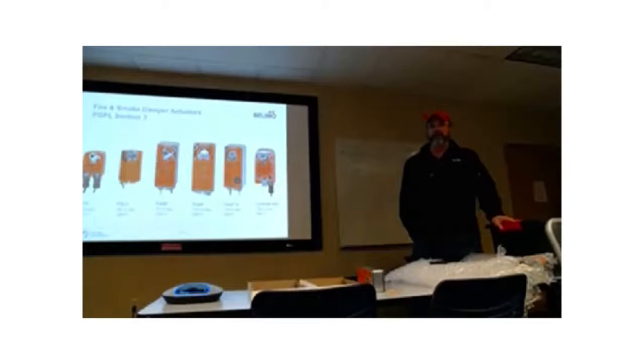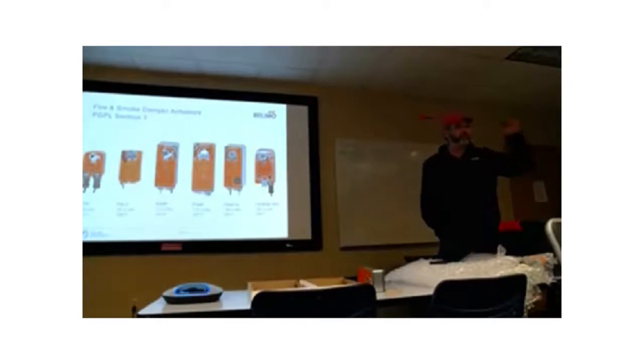We haven't had trouble, but if you ever do, we have one jurisdiction around here that balked on us. They said, nope, you must replace that actuator like for like. I got a chuckle out of it about a year and a half ago, that same jurisdiction relented and let the owner put in Belimo for replacing the fire smoke damper actuators after 8 years. I think what happened was the existing equipment kept failing every 2 years, and they got sick of replacing the dampers. So they finally came over to our side.